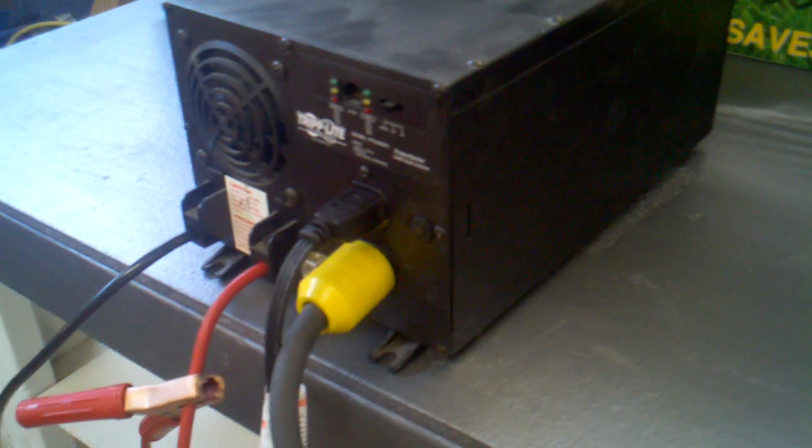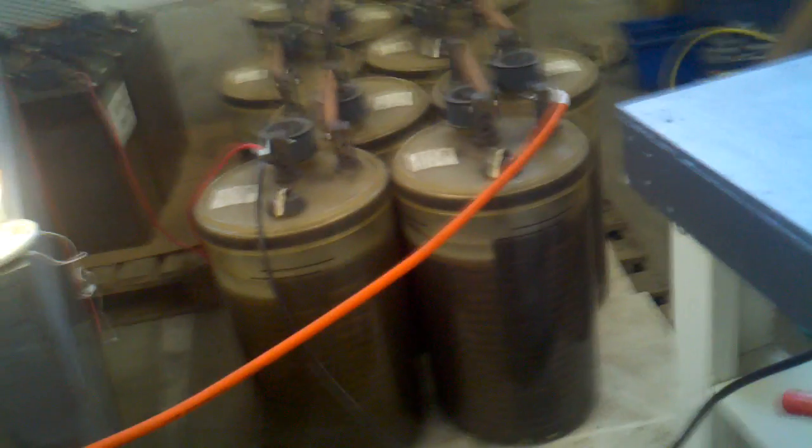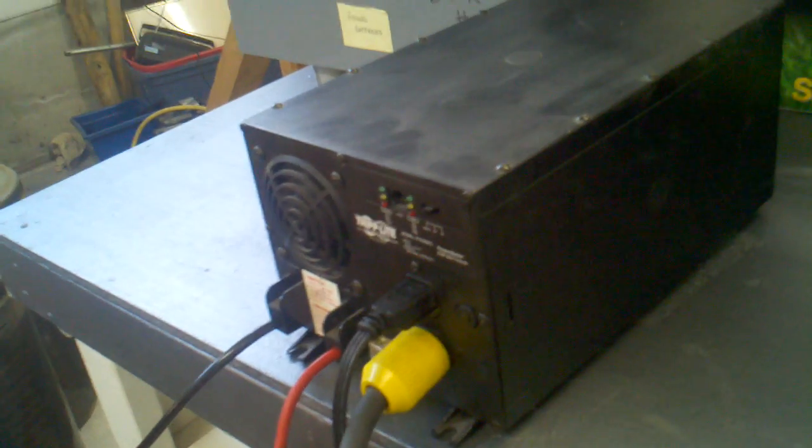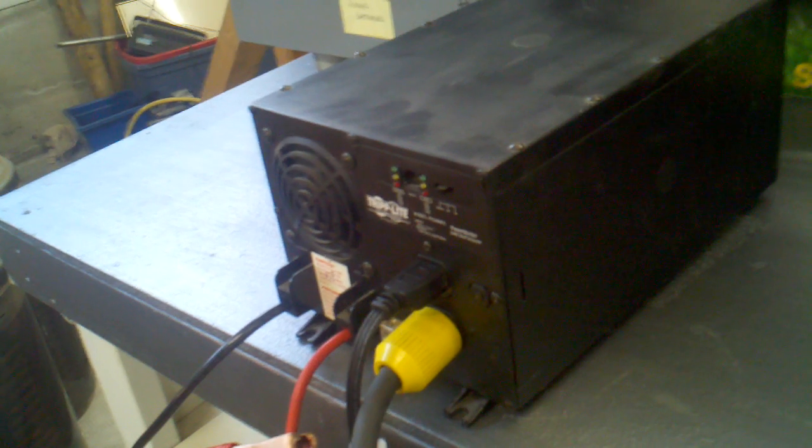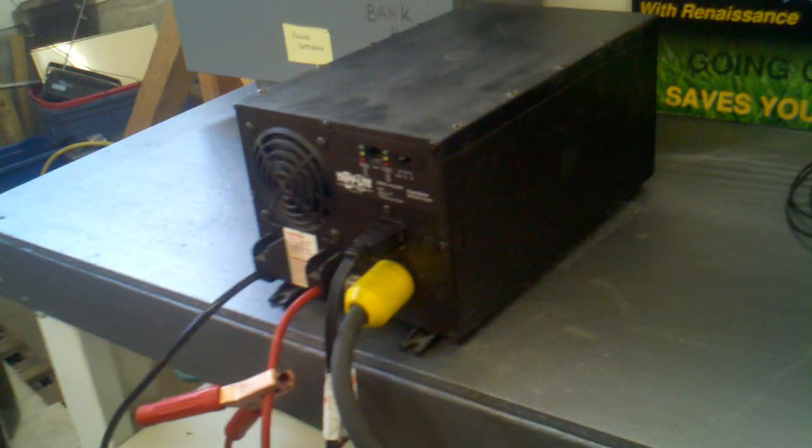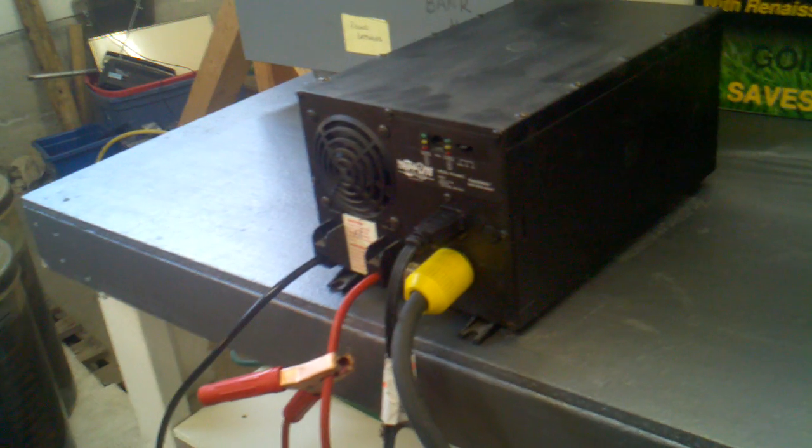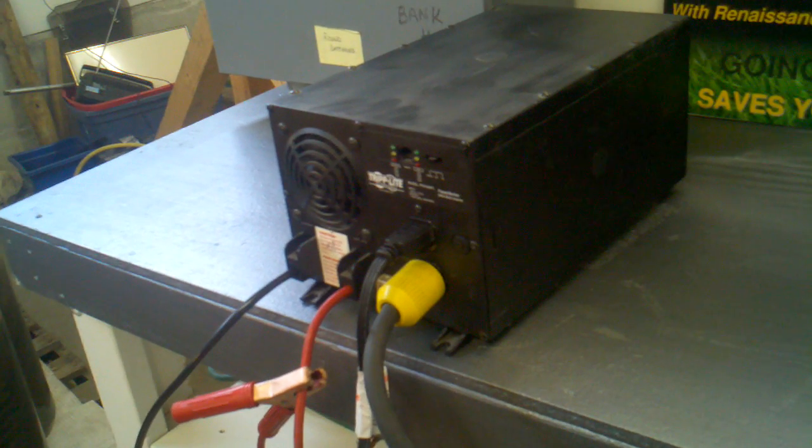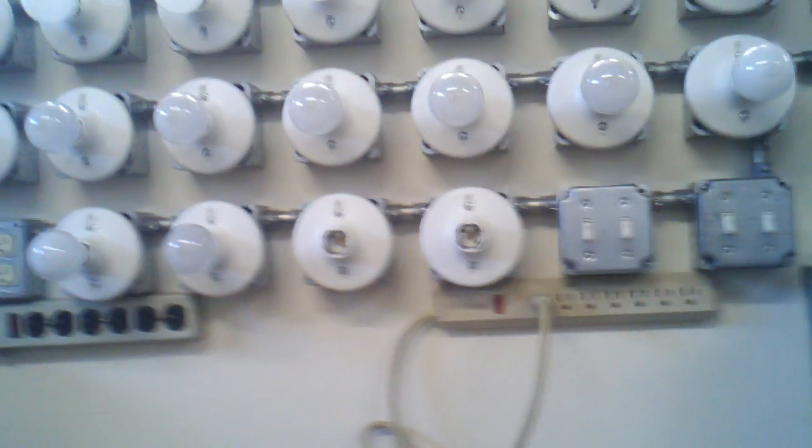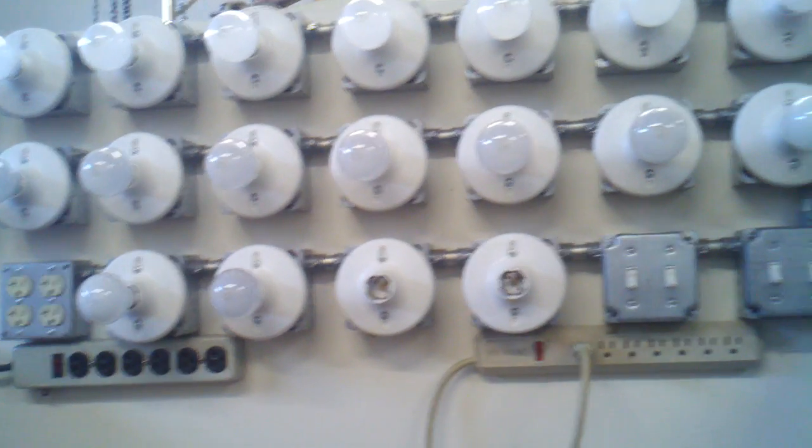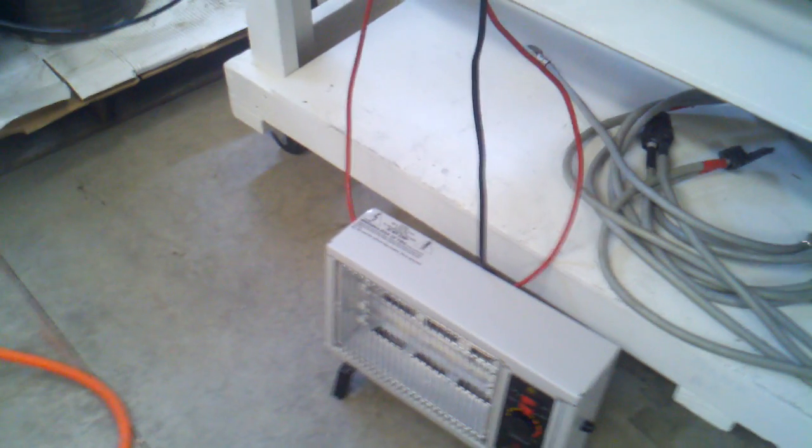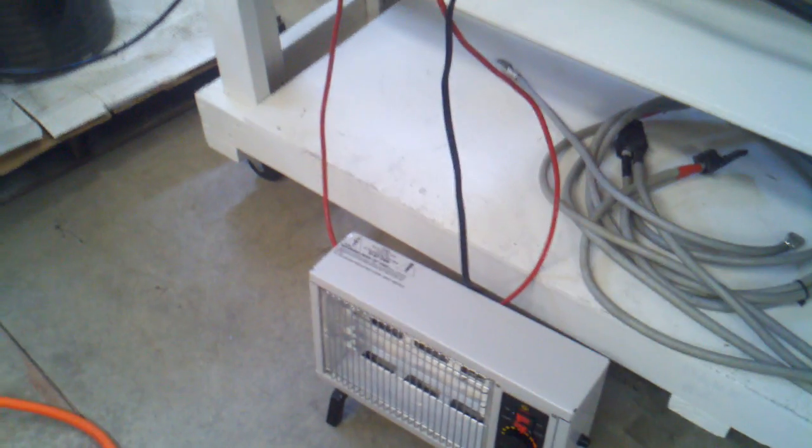This inverter we don't want to run directly while this is running because of the negative energy and the spikes will ruin the filtering system. Even though there's a capacitor bank and filter, it will still be negatively affected. So we're going to wait until we shut it off before we run the loads. But we've got almost 2200 watts of bulbs here, two missing I don't know where they went, and then we've got a 1500 watt heater here that we can run just to show they're running off of this bank right here.